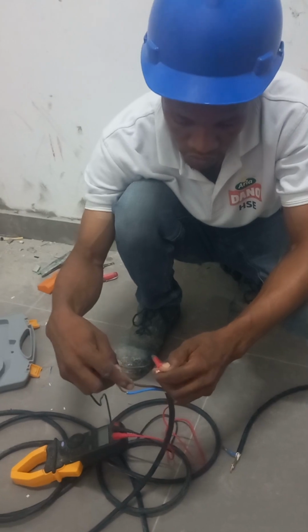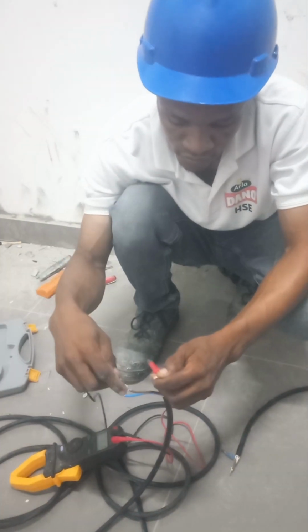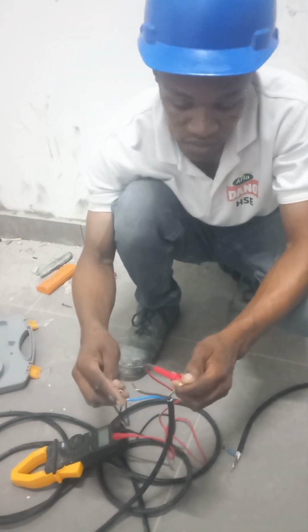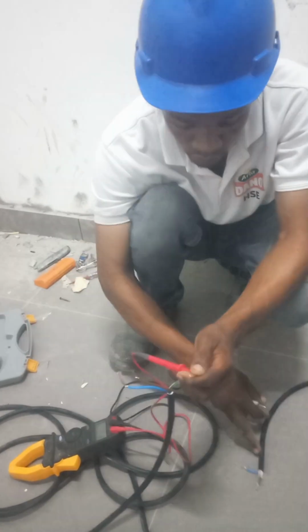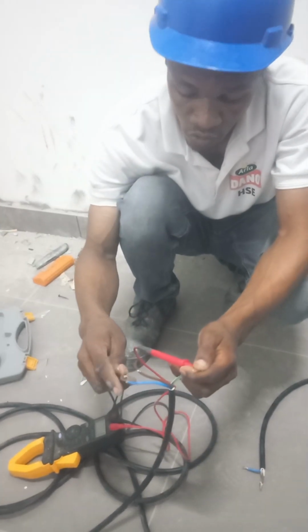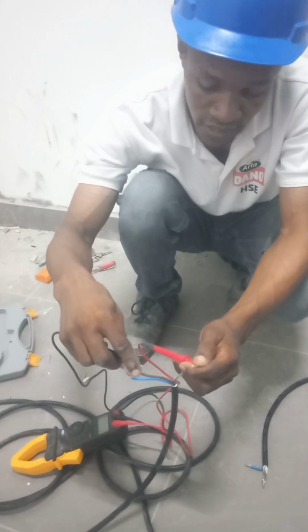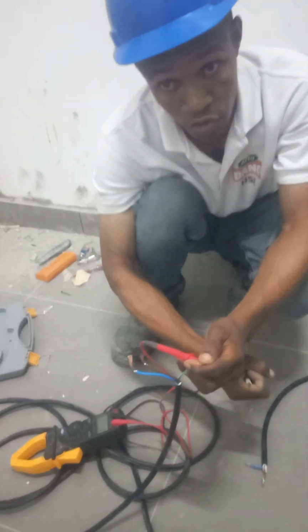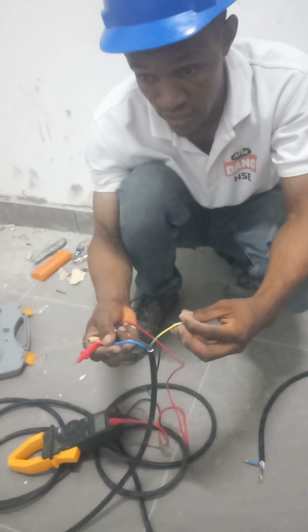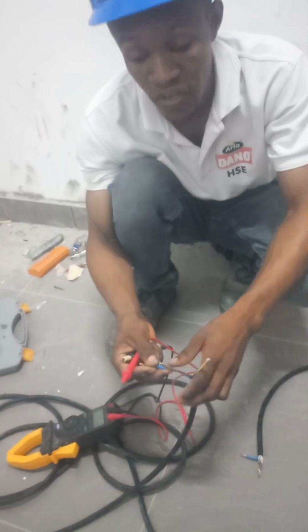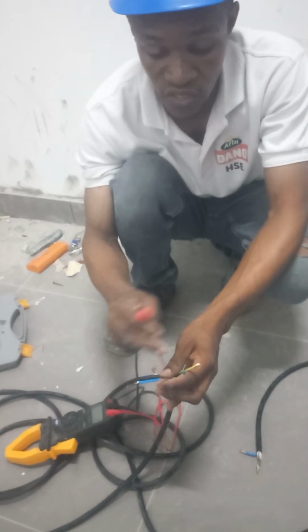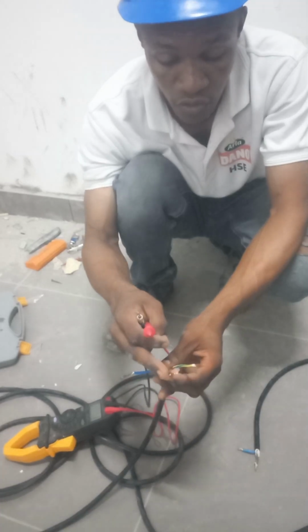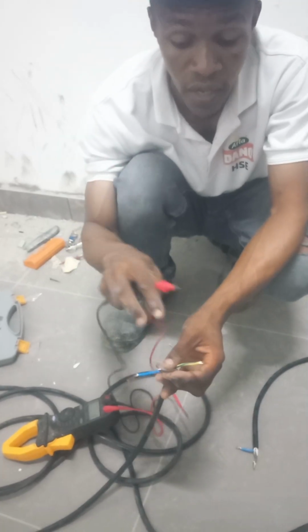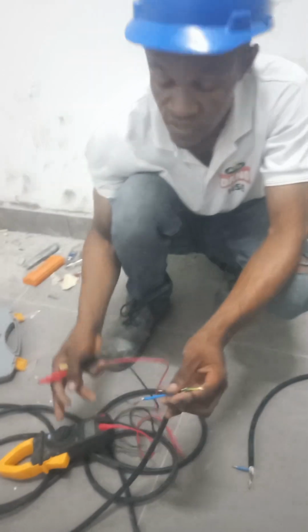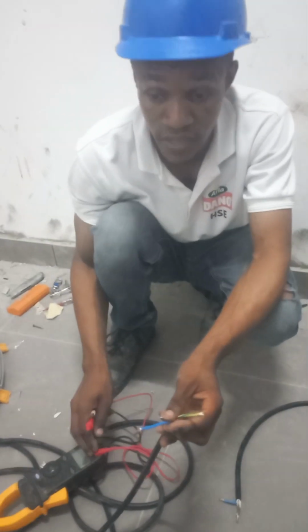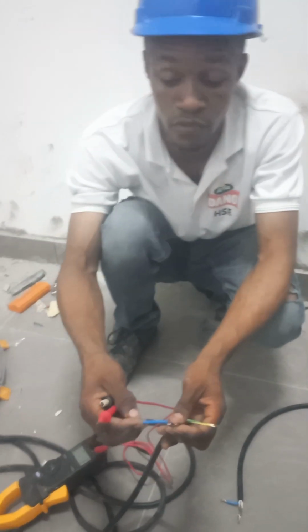So you see, now you put it here. It's not going to come because this blue is isolated. Yeah. If you just put it back here, it will come out because both of them are shorted. So each time you want to run a continuity test, even if it is one drum, find the end and join what you want to. If it is this yellow, this earth to brown, you want to check, you short it, you use your jumper, short it, and check. The multimeter or clamp meter will make noise. If it is brown and blue.